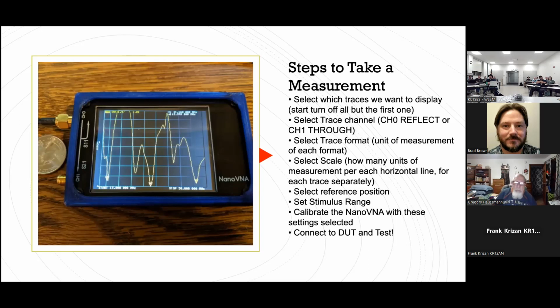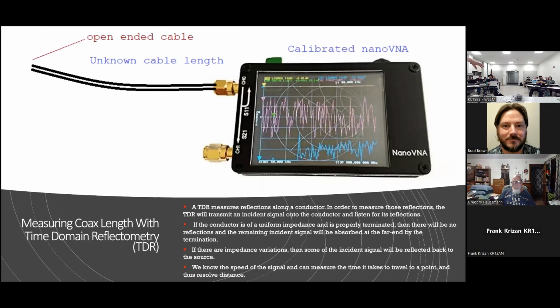But it is important that you set your stimulus before you do your calibration, because if you calibrate for 2 to 30 megahertz and then you're testing 140 to 150, all of your calibration is going to be completely irrelevant. It's going to do its best to extrapolate the data, but it's not looking at good information. And again, I'm going to walk through most of this in a little bit.